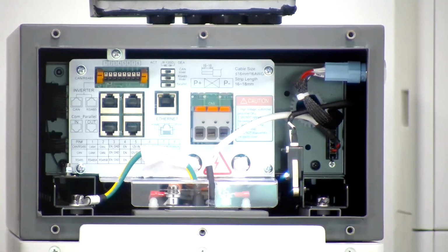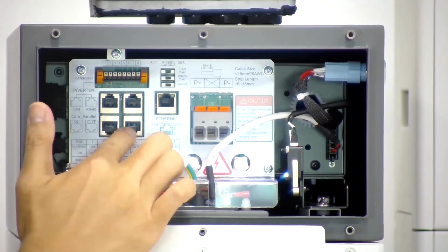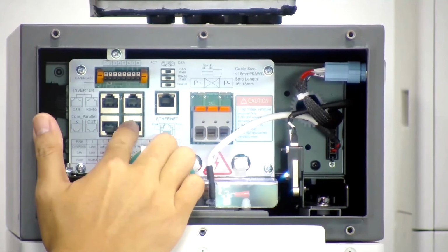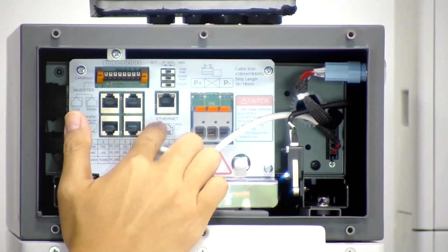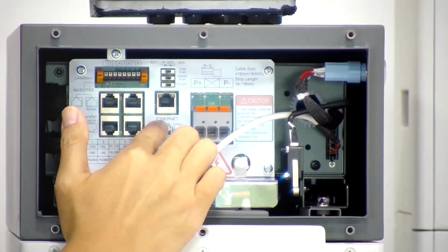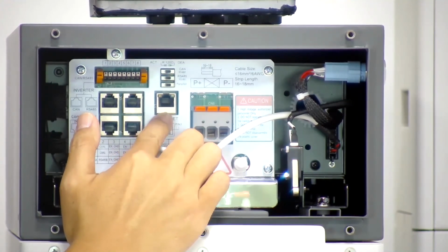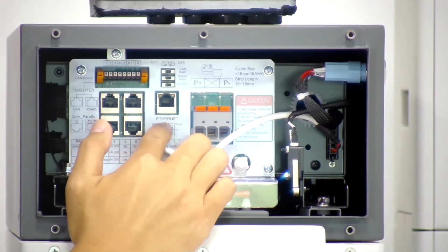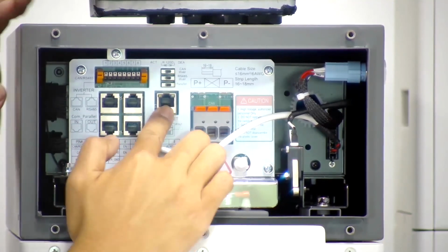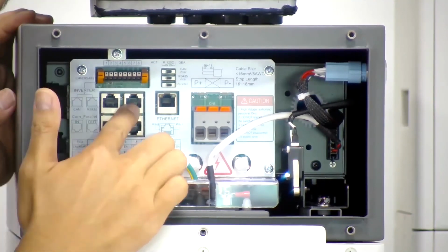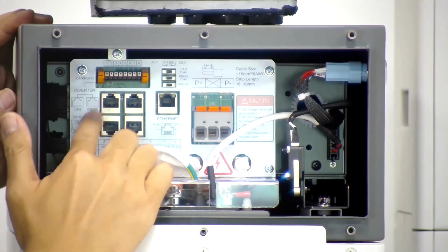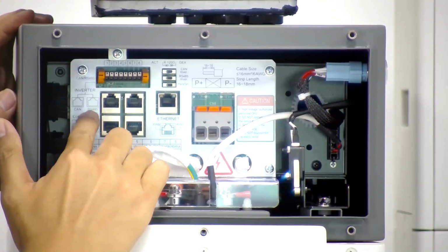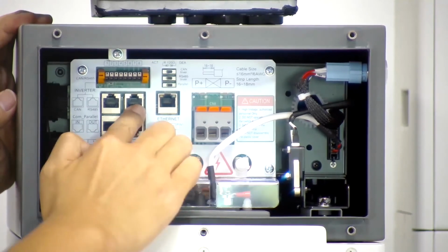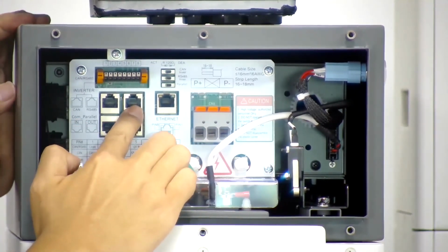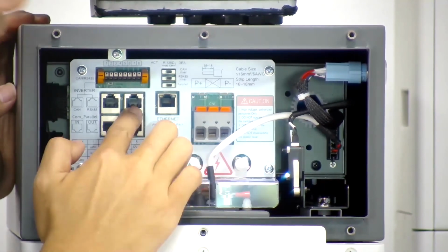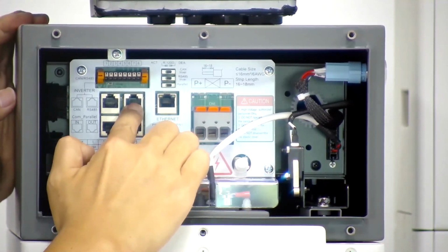Okay, let's go back to the communication ports. These are for parallel in and out. Then we have this Ethernet port, for connecting to the BYD server for remote firmware updating or troubleshooting. Then we have two ports to the inverter: on the left-hand side, the CAN port, and on the right-hand side, RS485. For instance, for Fronius Gen24, which is RS485, we use this port.